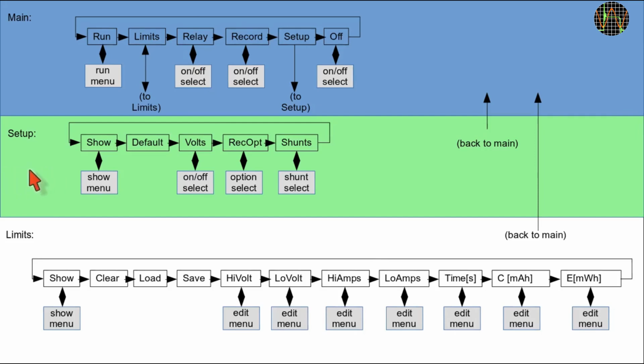The setup menu allows looking at the current settings using the show option, resetting to defaults, selecting the load or supply side voltage, changing the options for the recording, or selecting a different shunt resistor. All setup changes are automatically saved and restored for the next time. The limits menu allows setting and enabling of limits. Check for voltages, current, time, capacity and energy.